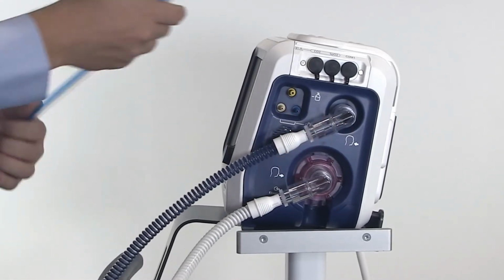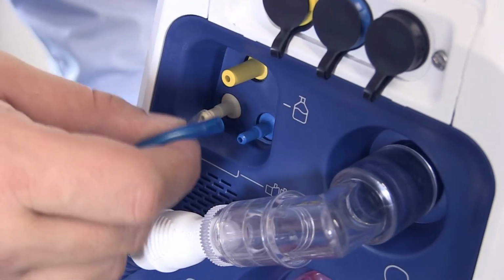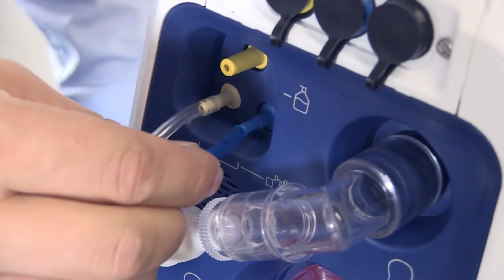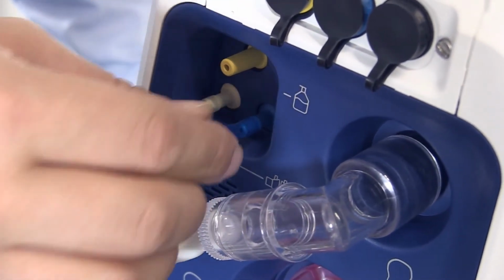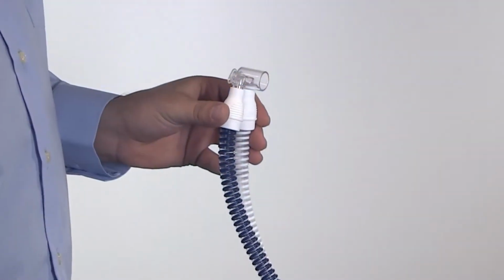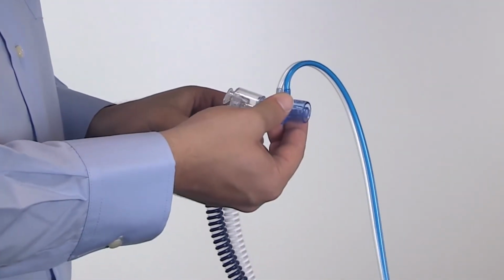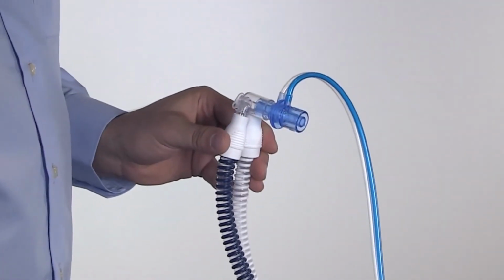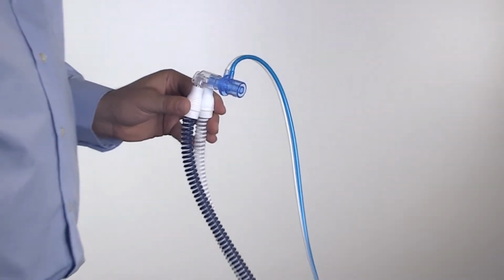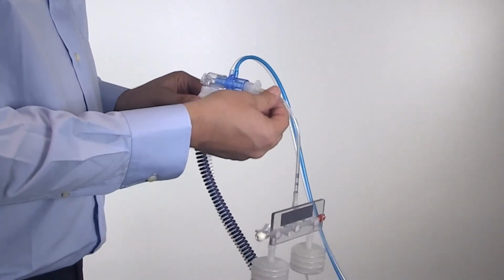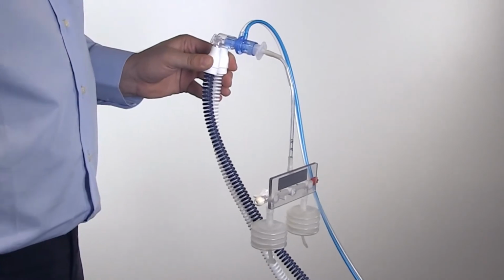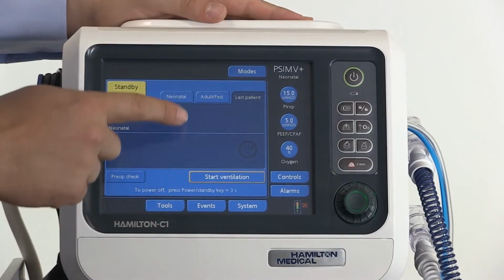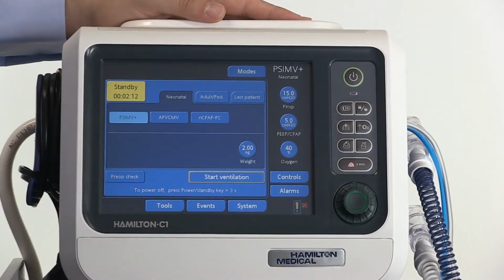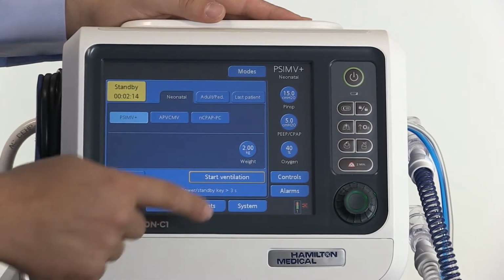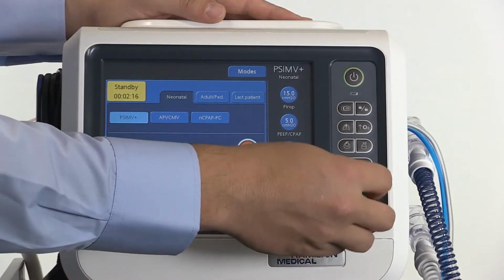Connect the tubes of the neonatal flow sensor to the device and connect the flow sensor with the Y-piece. Now take the neonatal test lung and connect it to the flow sensor. While in standby, select the neonatal option.